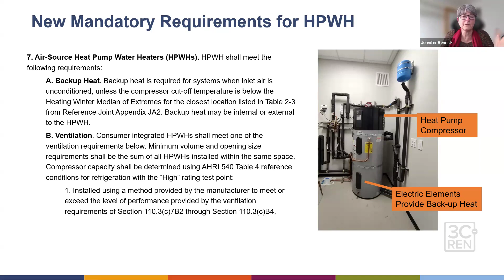Each of these heat pump water heaters requires air. It's referred to as ventilation, but it doesn't mean ventilated like fresh outside air. It's not that kind of ventilation. It just means there has to be enough air volume for the heat pump to take the heat out of that air and put it into the water. Then it ejects the cold air because the heat's been pulled out of that air. So in a very small confined space, it's possible that this appliance would continually chill the air and it would be too cold to function properly. So ventilation is a big part of it.